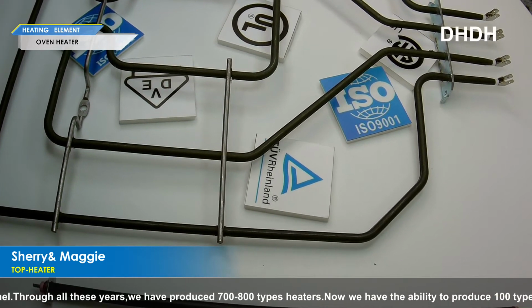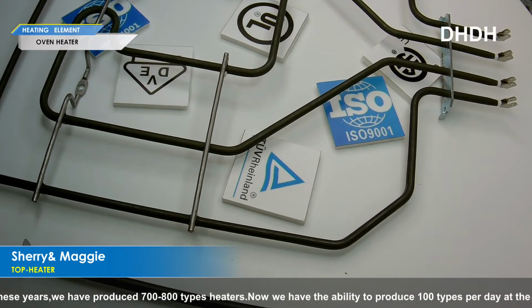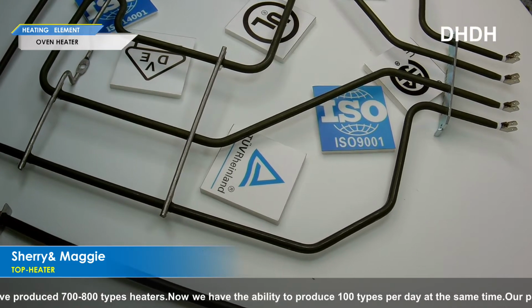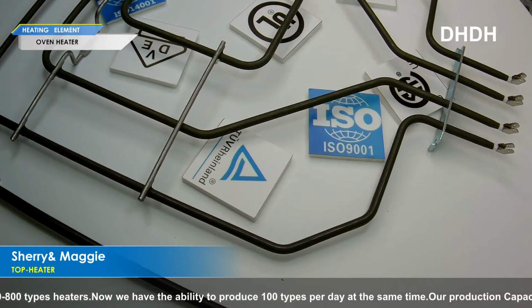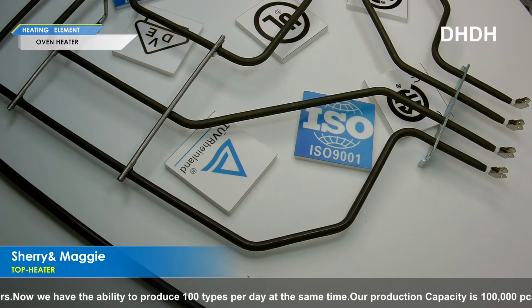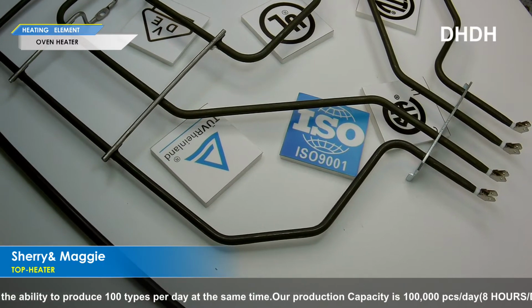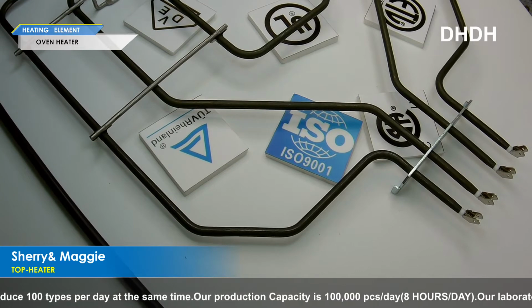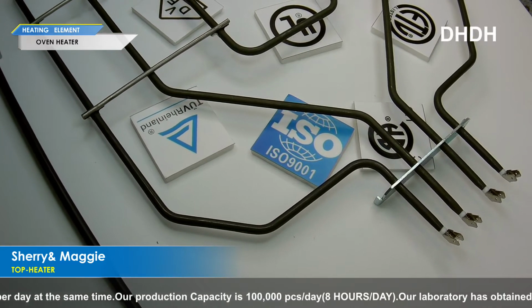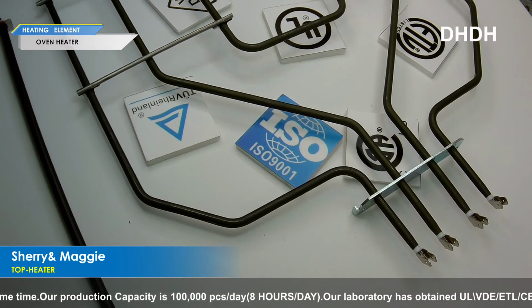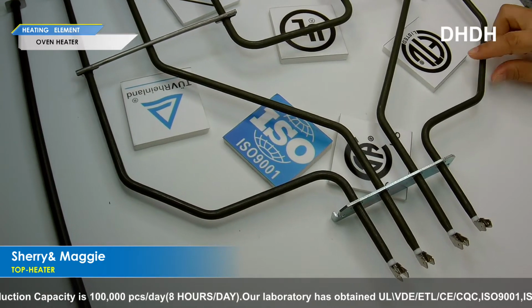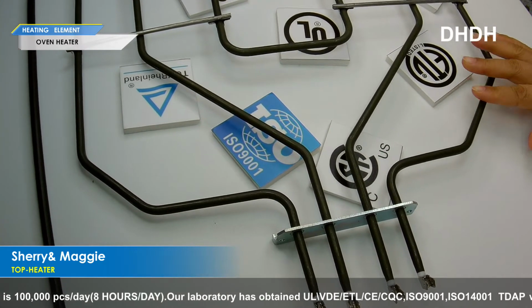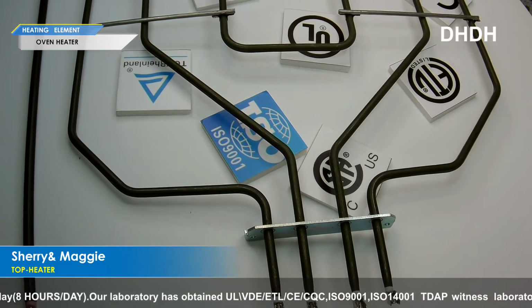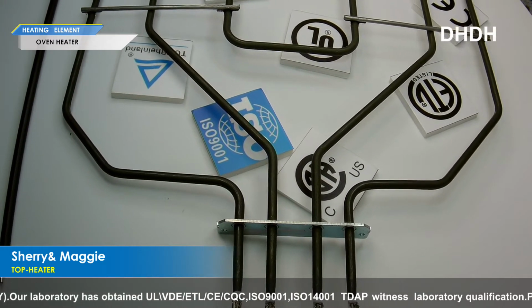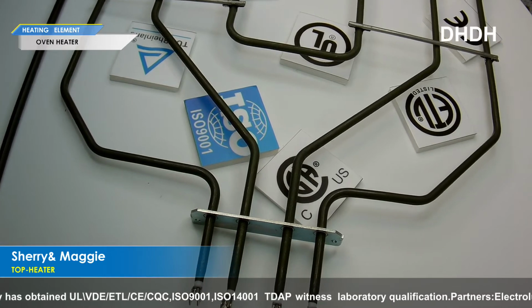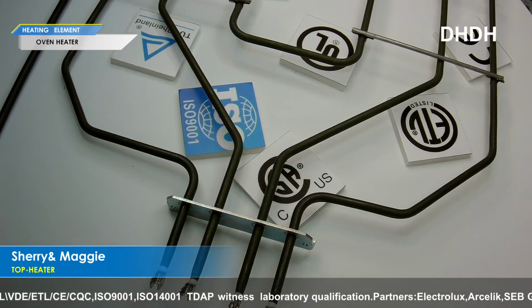Why? Compared with a heater heating in water, which transmits heat very fast, the oven heater works in air, and air transmits heat slowly. On the other hand, the surface loading of the heater is very high during high temperature working. That's why we need high grade tube material.